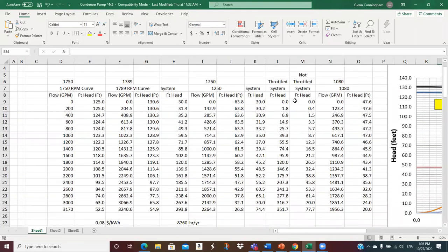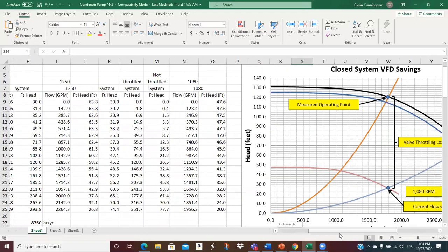So this was my pump curve. Okay, so I got a copy of this off a website, or the plant gave me a copy. This is 1750, a standard RPM, and this is just taking the pump curve, picking points from what the pump could do. So 0 GPM, 125 feet. It started out, it was just that first little bit was straight. So 200 GPM, 125, 400 GPM, 124.7, all the way down. Estimate it down. Okay. Then you can plot that.